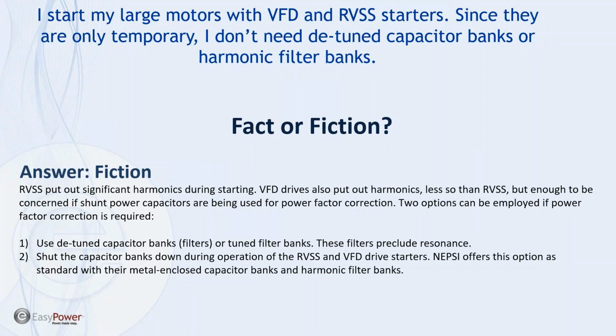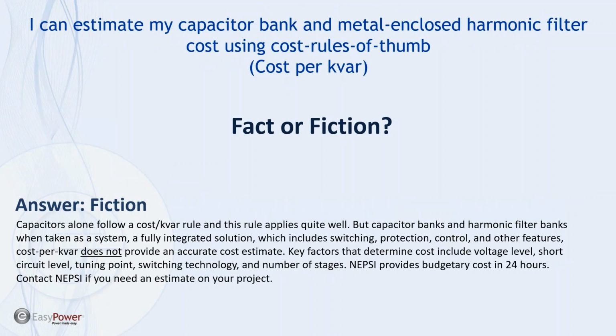So that's your choice. Okay, cost per kVAR is another myth that we often hear. Can I estimate my capacitor bank and metal-clad harmonic filter bank based on rules of thumb, cost per kVAR? We hear this quite often. The customer might call and say, I know my cost per kVAR is this, and if I double it, you can expect double the cost. This is simply not true. If you look at the capacitor alone, yes, you can apply a cost per kVAR rule of thumb. But if you're looking at an entire system which contains switching, protection, and control, you cannot use cost per kVAR. You need to consider all the cost factors.